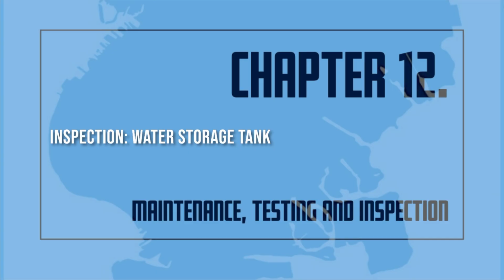The interior of all other types of tanks shall be inspected every 5 years. The tank interior shall be inspected for signs of pitting, corrosion, spalling, rot, and other forms of deterioration, waste material and debris, aquatic growth, and local or general failure of interior coating.